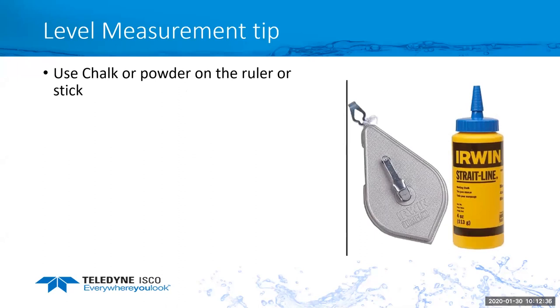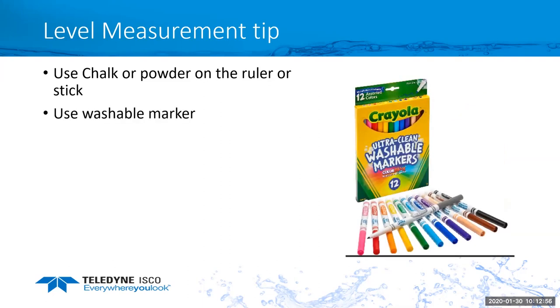A couple of tips I've seen when I've been out in the field with the technicians taking level measurements: they will use chalk or powder, put that on their ruler or stick, put that in the water, and then it's going to wash off where the water is, and then you just measure up to where the remaining chalk is. One I recently saw that I liked is they use washable markers. So they had a metal ruler or stick that they put in there, and they used the washable marker, put it on there, and the same thing. The water washed off the marker. You just measured up to where your ink was, and that was your level. Nice, easy way to do it that's less messy than using chalk.